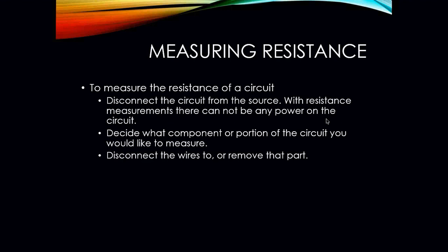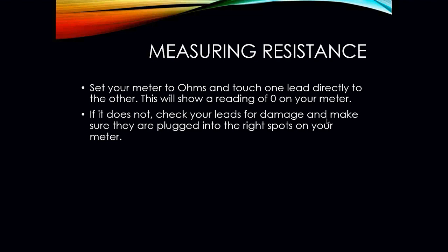To measure resistance, you want to disconnect the circuit from the source. Okay, make sure the power is off. With resistance readings, there cannot be any power on the circuit. Okay, if we leave the power on and we're taking a resistance reading, we can fry our meter, damage it in some way. Decide what component or portion of the circuit you want to measure. You are then going to disconnect all the wires from that part, and then set your meter to ohms.